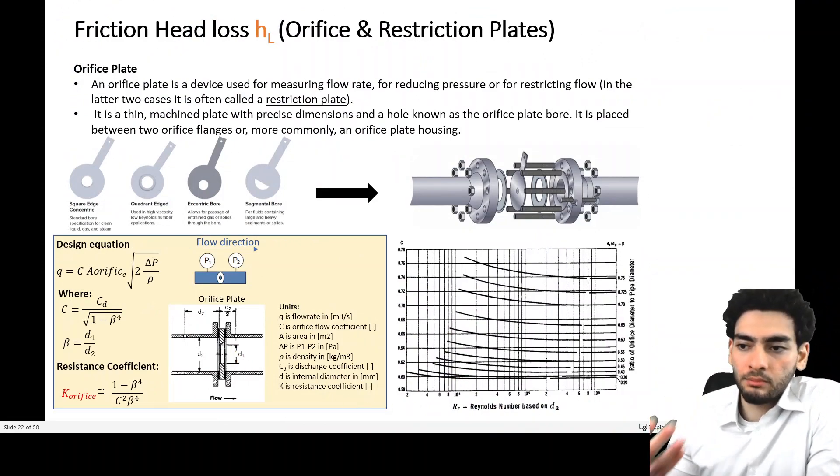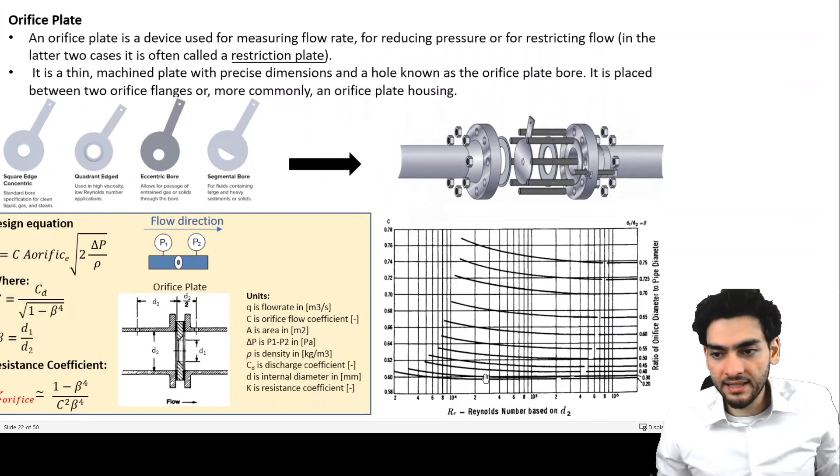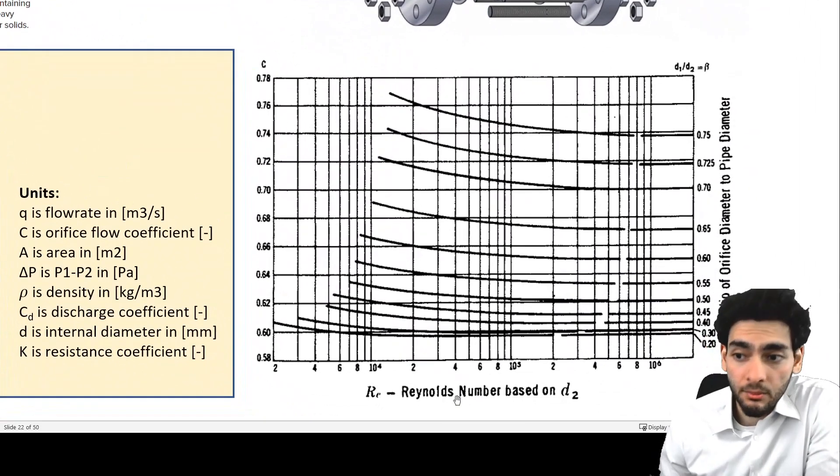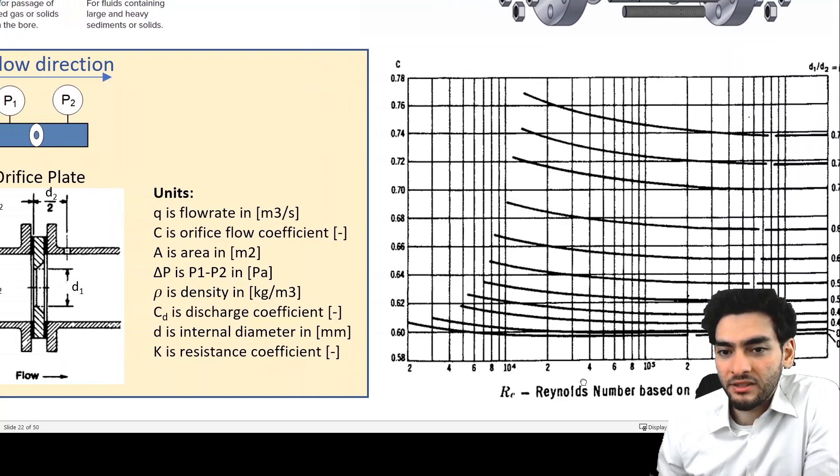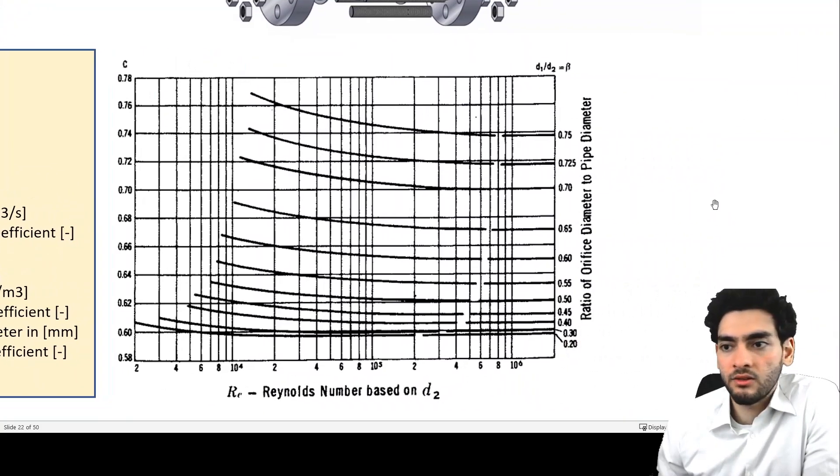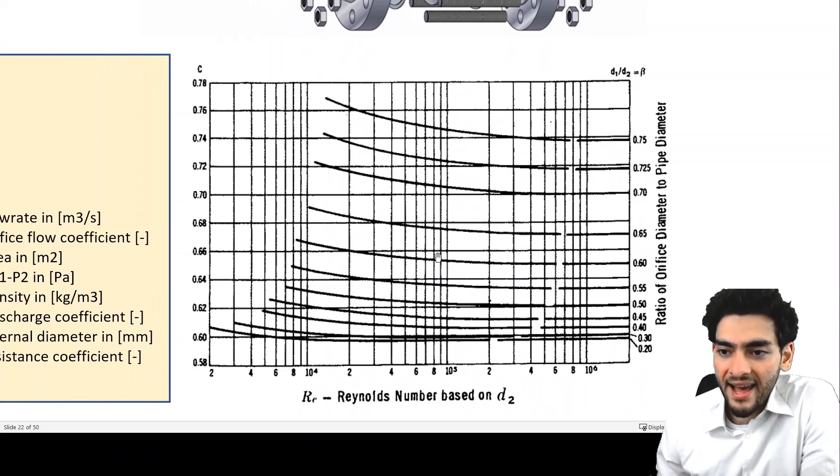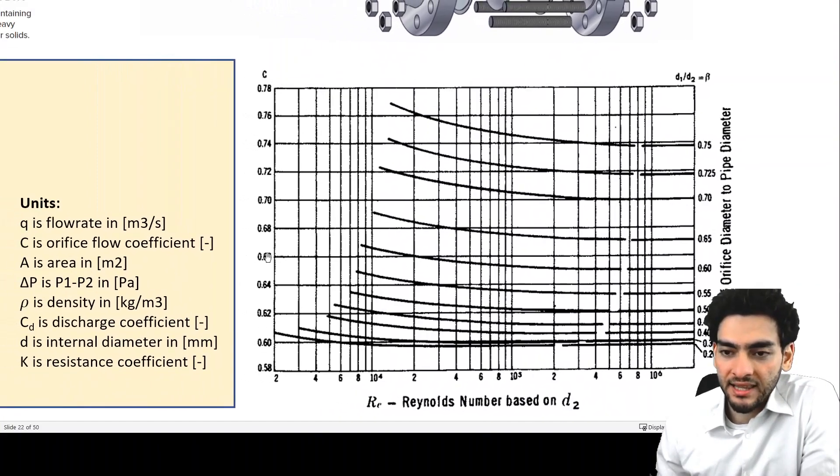The orifice flow coefficient is a function of the Reynolds number based on the diameter of the pipe on the x-axis. On the curves, you have beta, which is the ratio of the orifice diameter to the pipe diameter. Where you land, you're going to read the y-axis on the left-hand side.